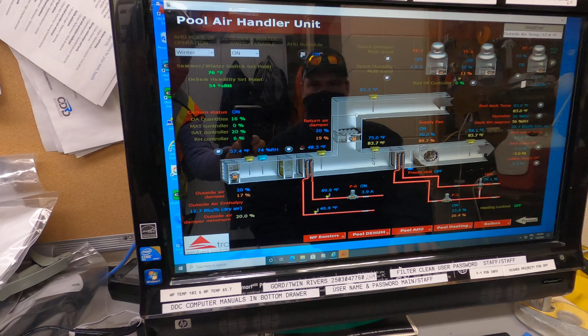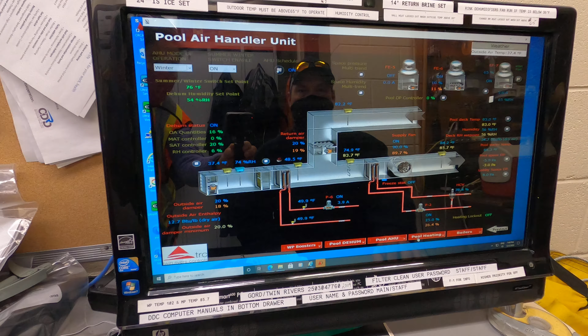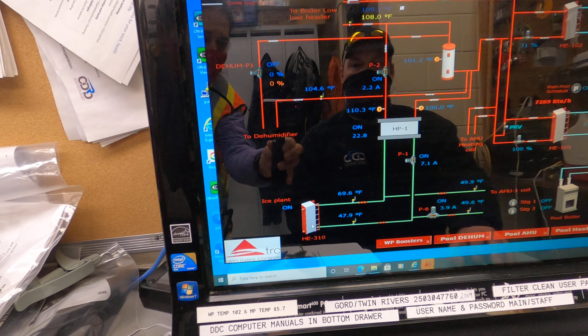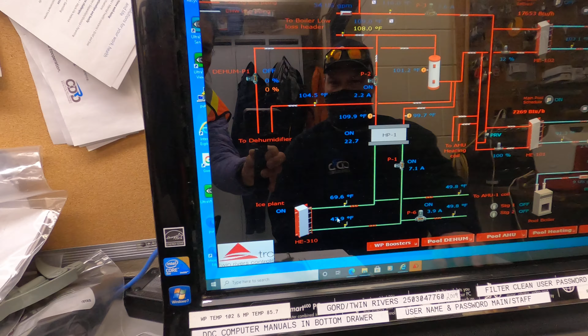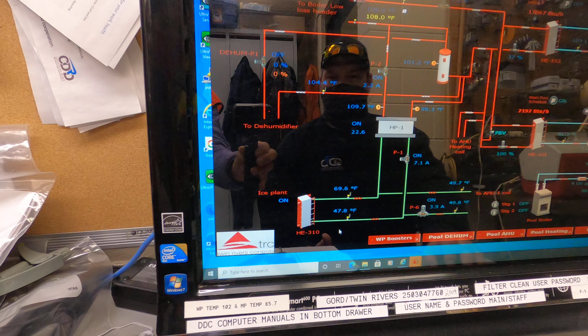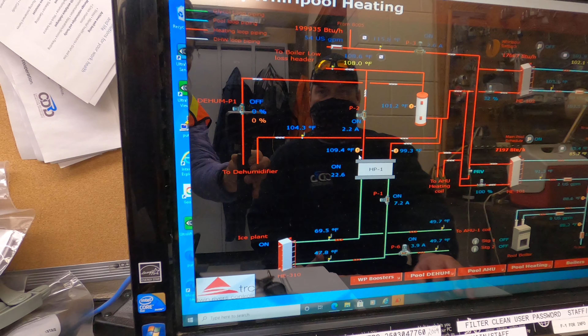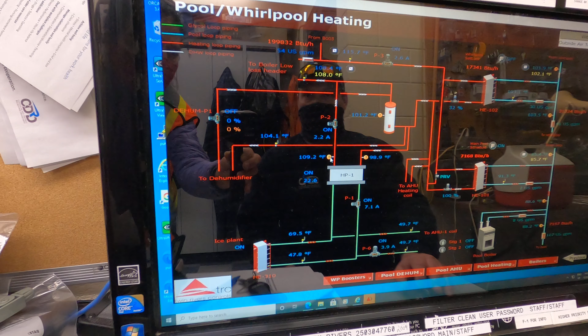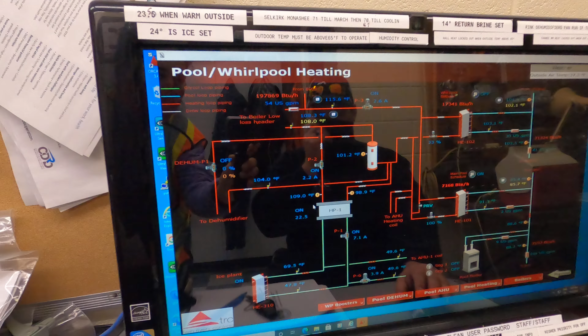We can click on these here. So this is just a graphical representation of what's going on right now with my pool air handler. Same with my pool heating. So this will show me here's my heat pump and that heat exchanger in the ice plant. And right now I'm sending 69.6 degree Fahrenheit brine to the heat pump, and it's coming back at 47.8, and it's supplying 109 degree temperature into my heating loop for boilers and building heat. So you can see there I'm almost doubling my heat through that heat pump.